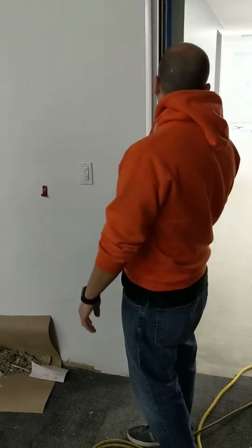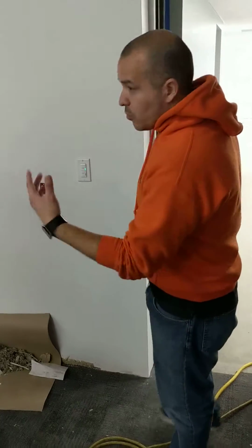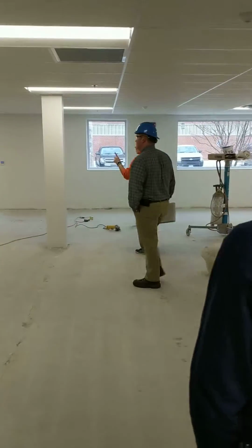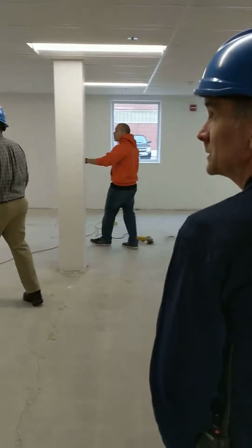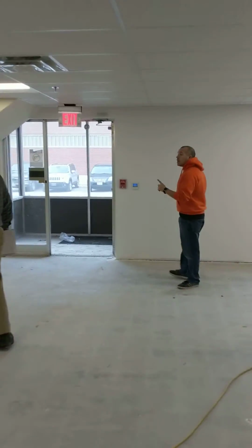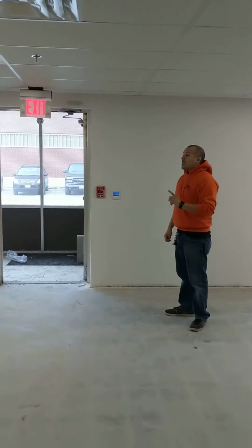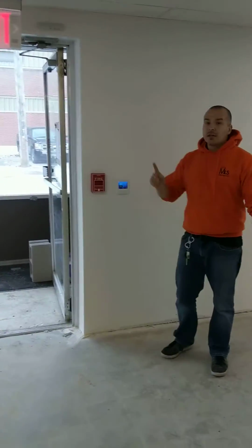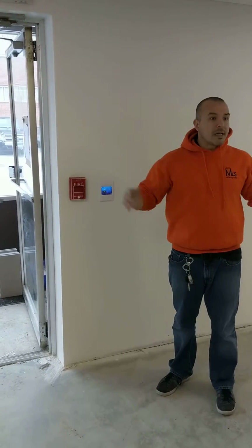Okay. So, did you want to walk and see the mezzanine? It's one graphical wall pod with an on-off switch. The room itself is going to act like one gigantic sensor. They're all set to the current energy code of 30 minutes max, so they will have a 30-minute timeout. As long as any one sensor sees motion, they'll all stay on.